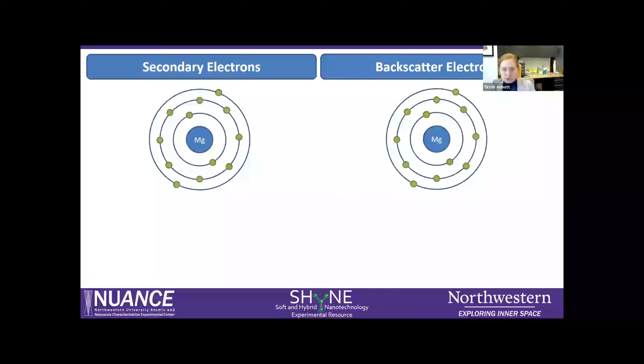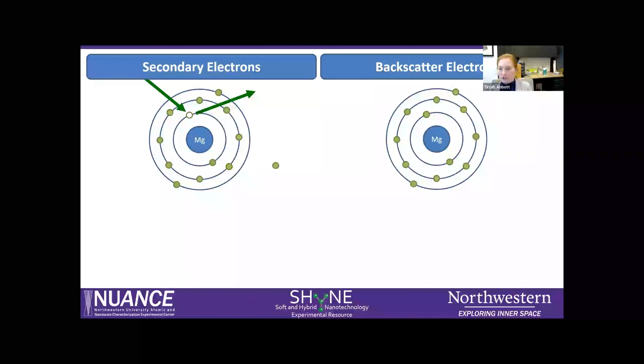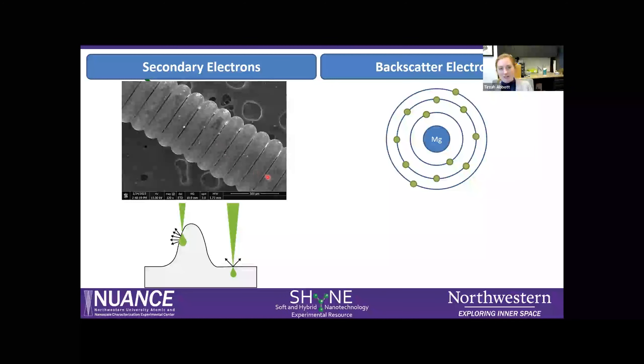The two most commonly used imaging signals in an SEM are secondary electrons and backscattered electrons. Secondary electrons result from inelastic interactions of the electron beam knocking out loosely bound electrons. They are very low energy and can only escape from the near surface of the material. More secondary electrons escape from edges in highly topographic materials, so the secondary electron signal is primarily used to get surface information or topography. This guitar string image shows the surface texture and brighter regions where more signal escapes, revealing nice topographic features.